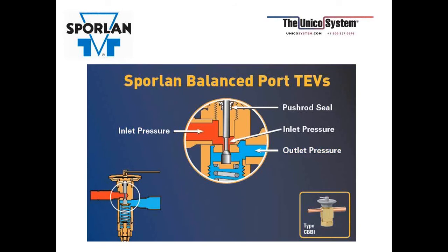We can negate this opening force by using a balanced ported valve. In this case, right underneath, on the push rod itself, you can see an area that's been milled away. It's a little thinner. That surface area underneath that lip is the same surface area as the angle of the pin. So then you have high pressure pushing up underneath the lip as well as pushing down on the pin, and it puts the valve in a balanced port position. And it has better control for low load situations. It can throttle down to about 25% of rated capacity. And it also has the ability to control over a larger range of conditions.